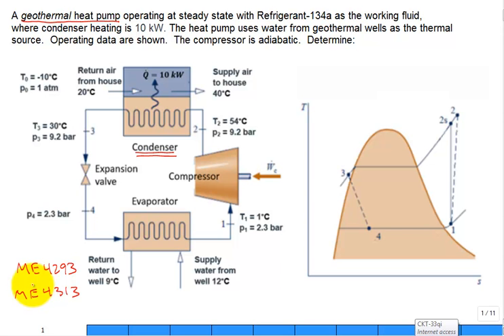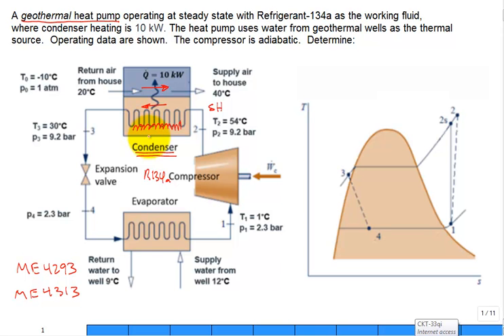When you have a heat exchanger that is counter-flow — so on one side fluid is flowing one way and the other side it's flowing the other way — and one of the fluids is undergoing a phase change. Here in the condenser, the refrigerant 134A enters as superheated. It spends quite a bit of time inside the condenser changing phase, going two-phase from saturated vapor to saturated liquid, and then it comes out as sub-cooled liquid.